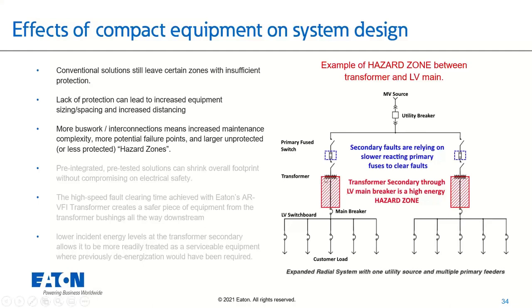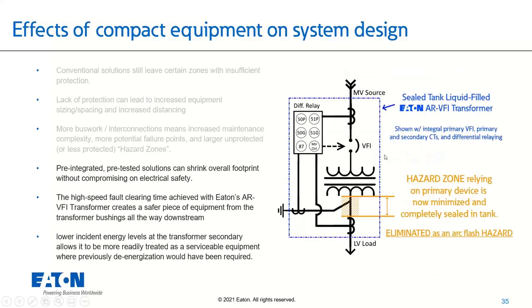But if you want to improve that system, if you want to make this into a reduced zone, that's where something like the AR-VFI transformer, or even, in a more traditional sense, a vacuum interrupter with secondary relaying comes in. I show here differential relaying, just so we're covering our primary, covering our secondary, perhaps some differential in the inner zone. But everything downstream of that secondary set of CTs is much, much safer.